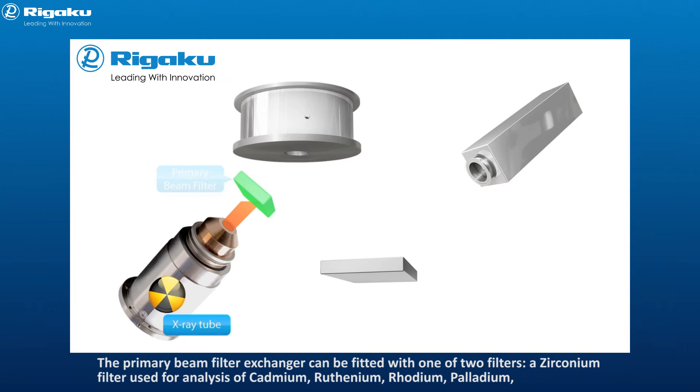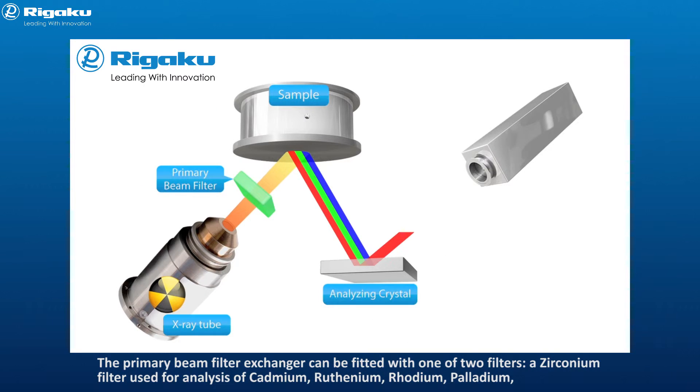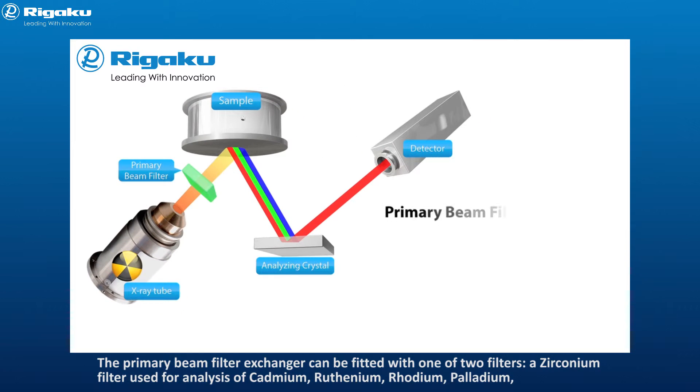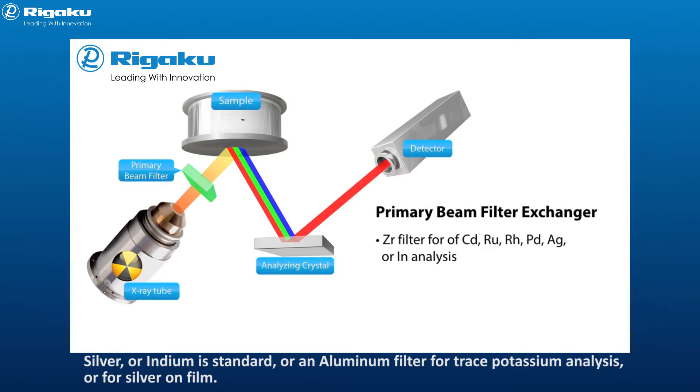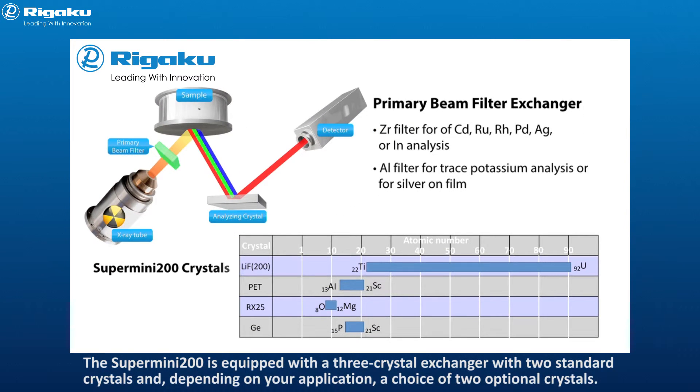The primary beam filter exchanger can be fitted with one of two filters: a zirconium filter used for analysis of cadmium, ruthenium, rhodium, palladium, silver, or indium is standard, or an aluminum filter for trace potassium analysis or for silver on film. The Supermini 200 is equipped with a three-crystal exchanger with two standard crystals and, depending on your application, a choice of two optional crystals.